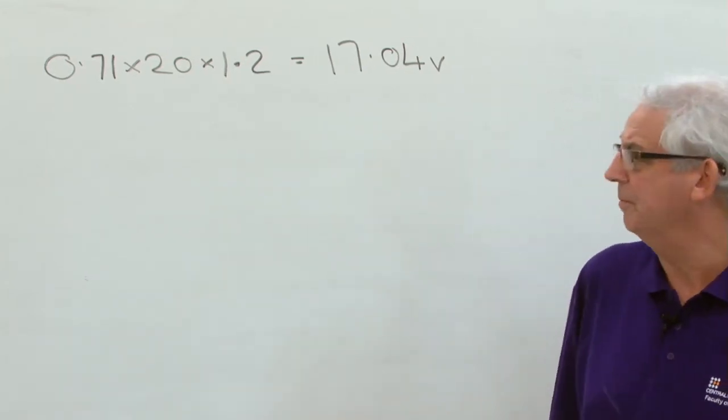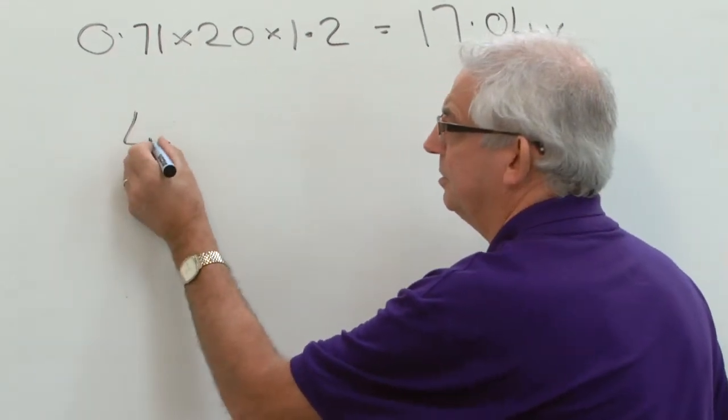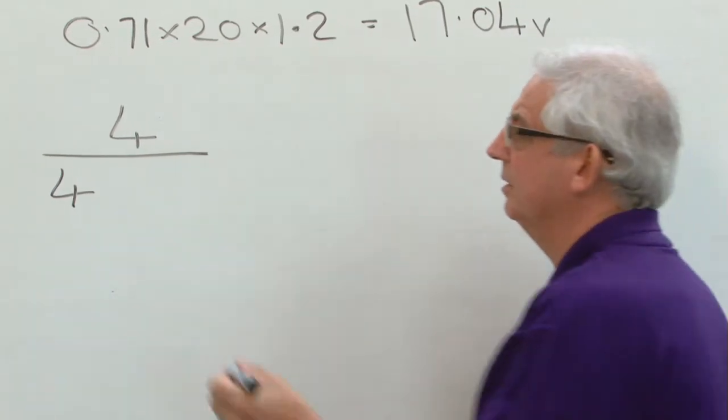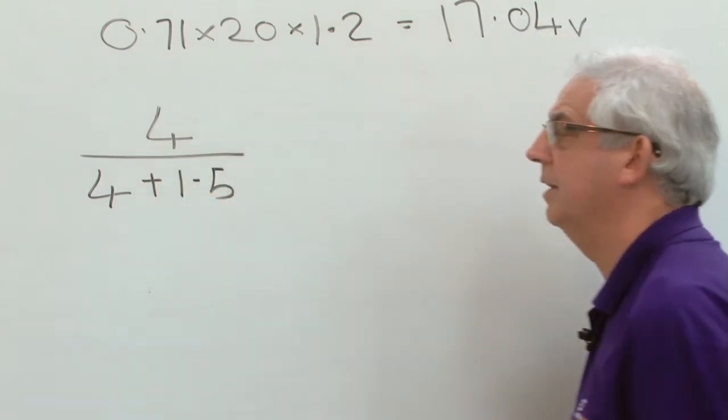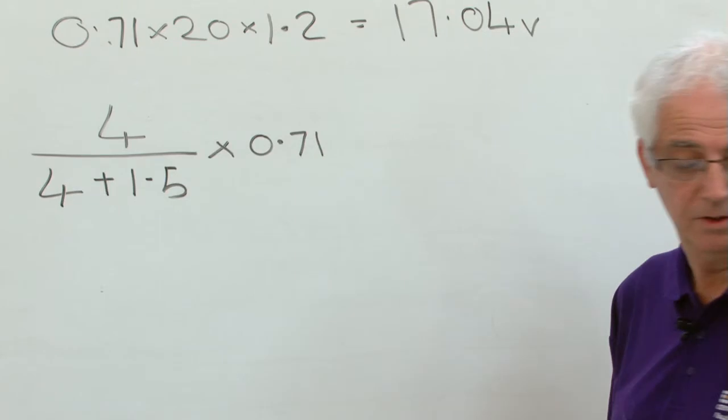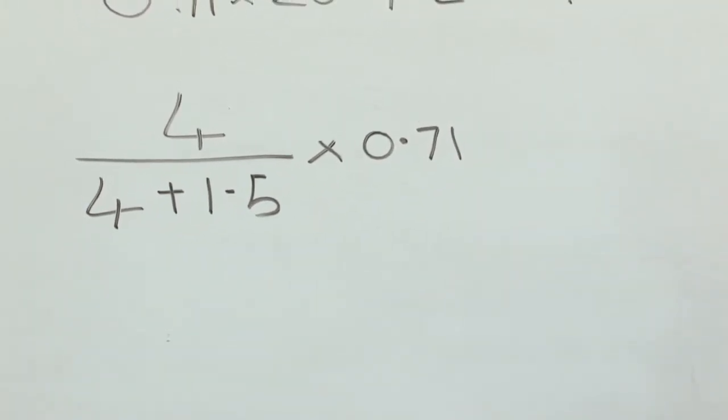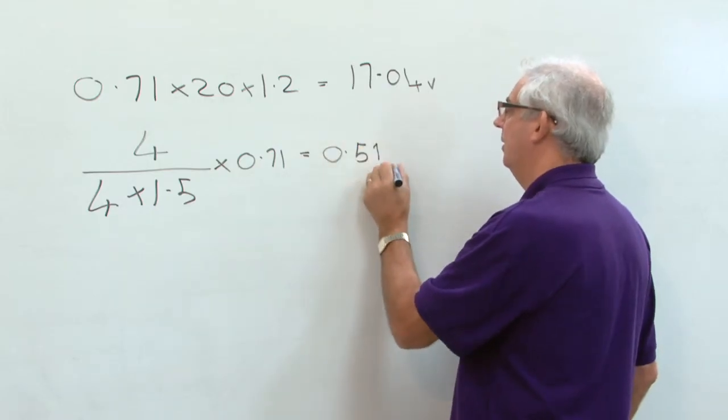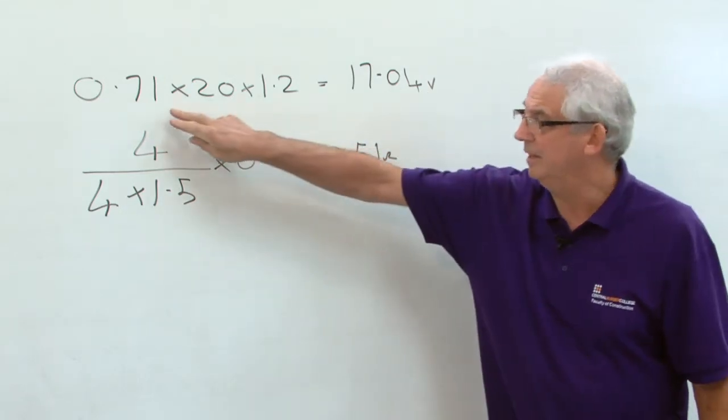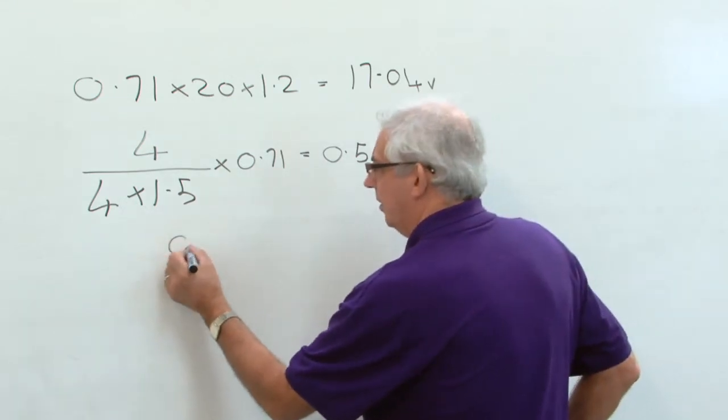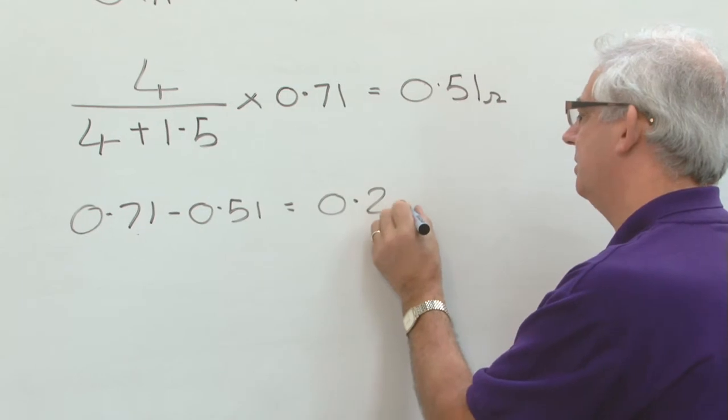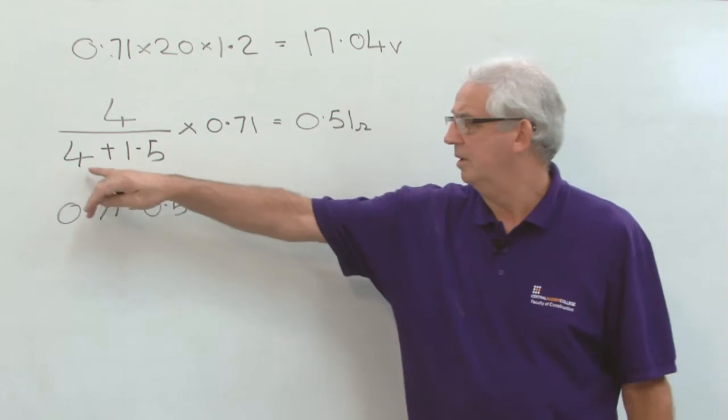It's quite a simple calculation, all I need to do is to divide the cross-sectional area of the CPC by the cross-sectional area of the line conductor plus CPC. I then need to multiply it by my R1 and R2 value which I've got there. That's going to come out at around 0.51 ohms. This 0.51 ohms is the resistance of my CPC in this circuit. If I have an R1 and R2 of 0.71 and I take away 0.51, it gives me a resistance value of 0.2. 0.2 will be the resistance value of my line conductor.